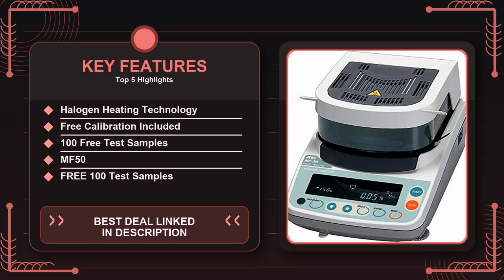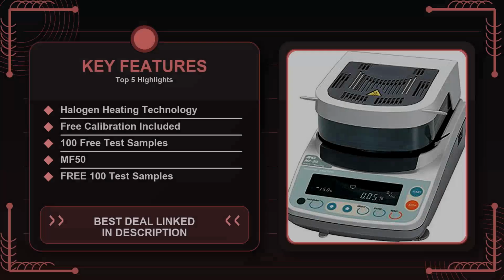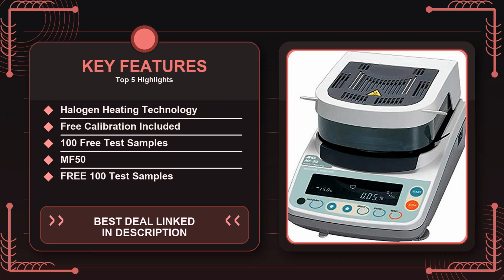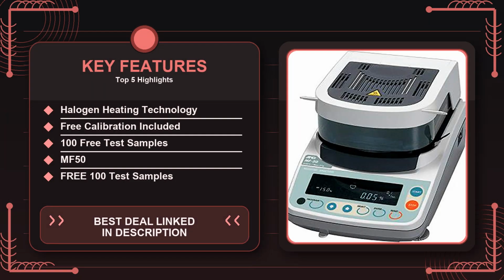On the flip side, if you're looking for a high-throughput industrial solution that can process dozens of samples per hour, or if you need a device with built-in robotic handling, the MF50 isn't built for that scale. It's a benchtop instrument, so you'll still have to manually load each sample, which can become a bottleneck in a large production environment. Likewise, if your primary need is measuring moisture in very high-temperature processes, say, metal casting, halogen heating won't reach the temperatures required, and you'd be better off with a specialized furnace-linked analyzer.